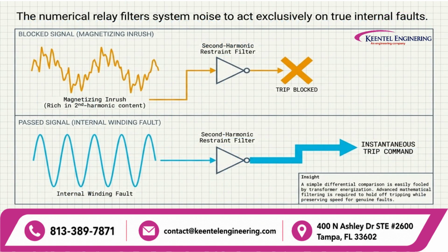One of the classic challenges in transformer differential protection is distinguishing magnetizing inrush from a genuine internal winding fault. During transformer energization, magnetizing inrush can produce a very large current. The important characteristic is that inrush contains significant second harmonic content. A numerical relay can analyze the waveform and apply a second harmonic restraint or blocking function. When the relay identifies the characteristic harmonic content associated with magnetizing inrush, the differential trip is blocked. This prevents the transformer from unnecessarily tripping during normal energization.